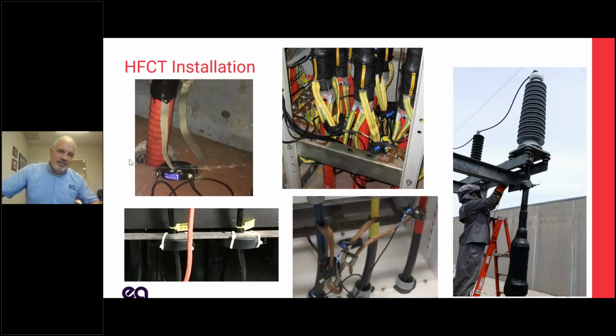Here are some examples of HFCT installation, some permanent installation, some temporary testing installation, and my favorite from quite a few years back is the old put on the bomb suit, go right up to it and install it live. We don't do that a whole lot anymore. Permanent install of HFCTs is more common, but there's usually a way to get an HFCT on the ground strap.